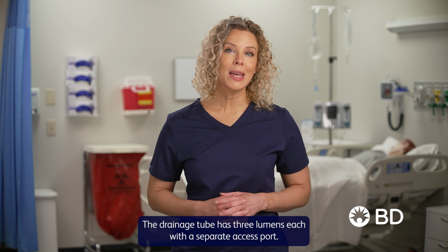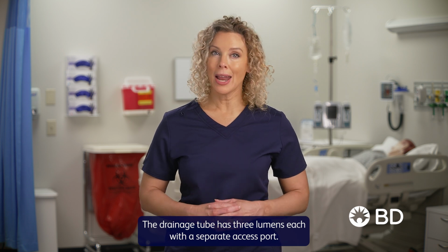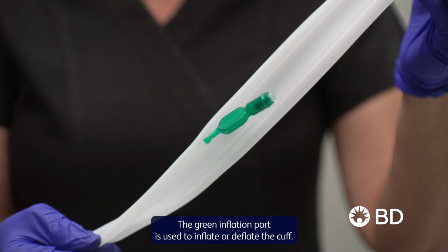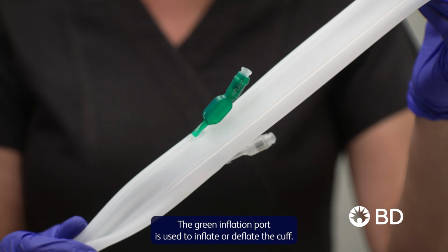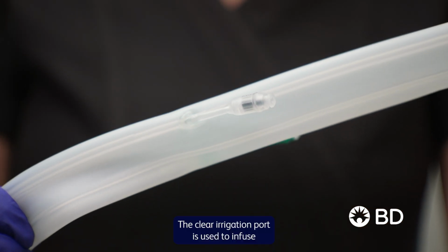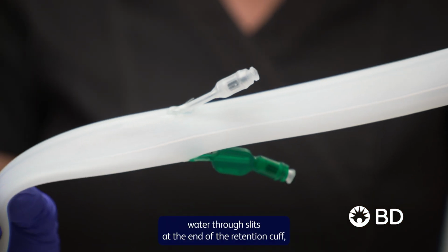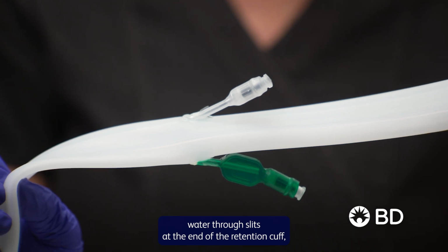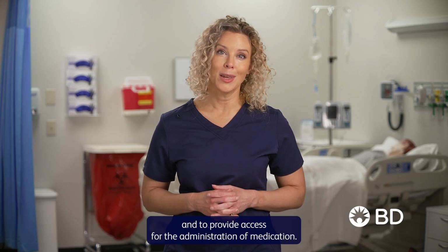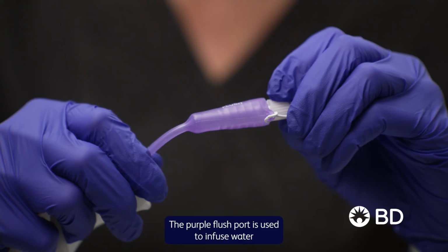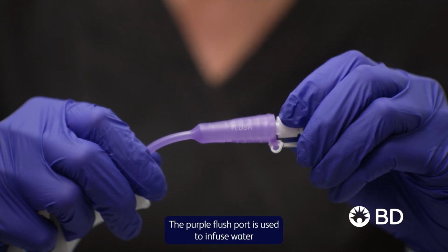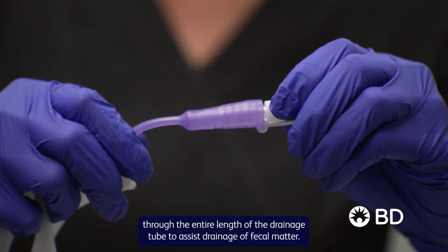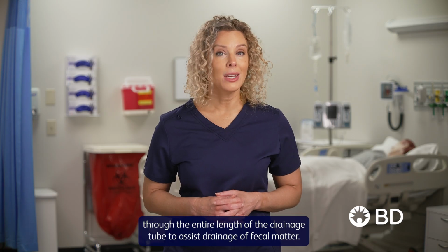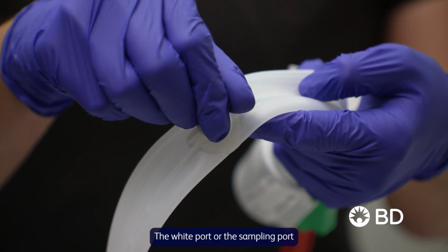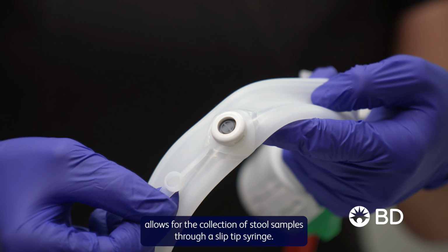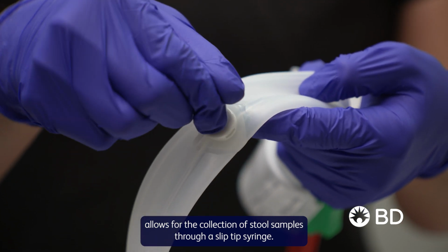The drainage tube has 3 lumens, each with a separate access port. The green inflation port is used to inflate or deflate the cuff. The clear irrigation port is used to infuse water through slits at the end of the retention cuff and to provide access for the administration of medication. The purple flush port is used to infuse water through the entire length of the drainage tube to assist drainage of fecal matter. The white port, or the sampling port, allows for the collection of stool samples through a slip-tip syringe.